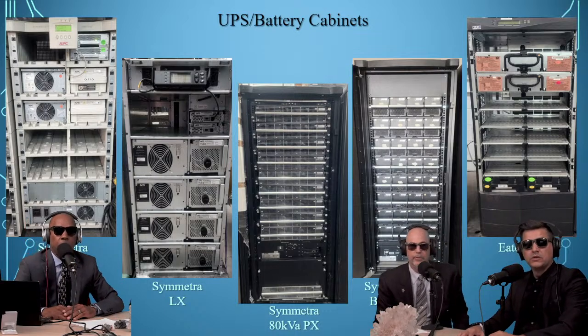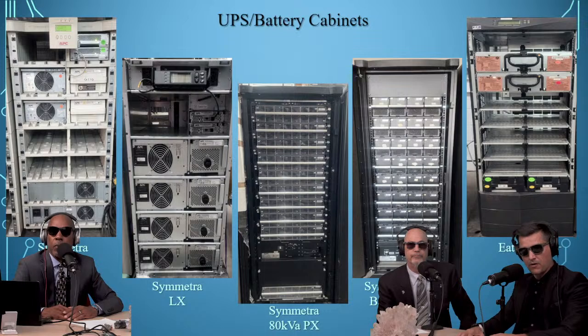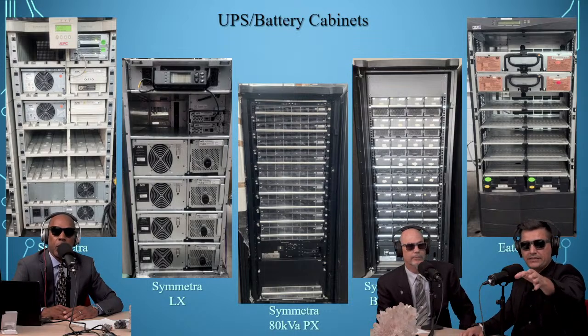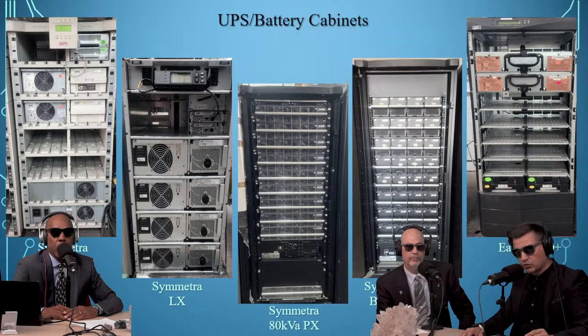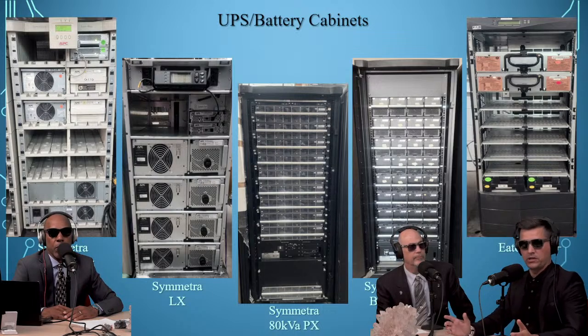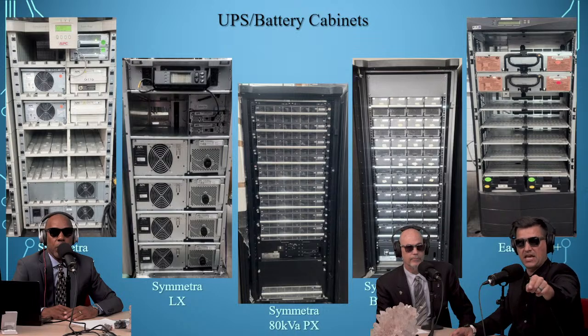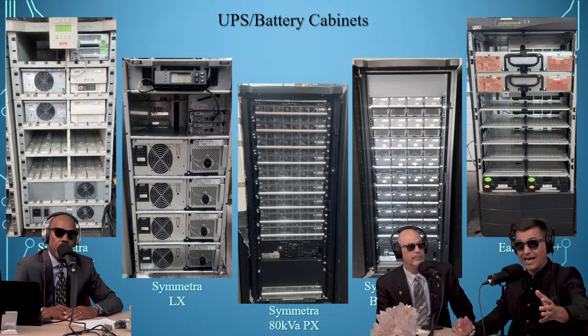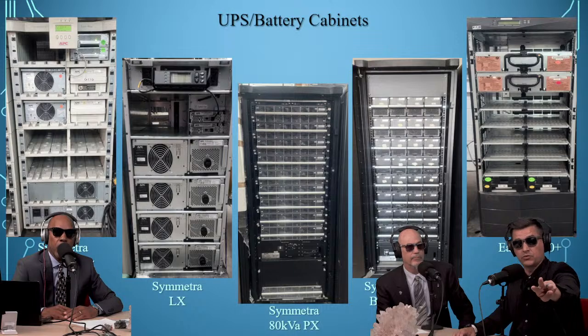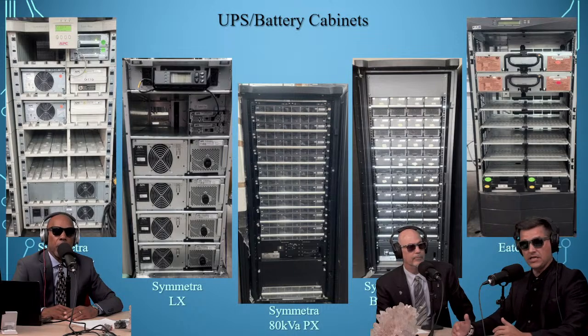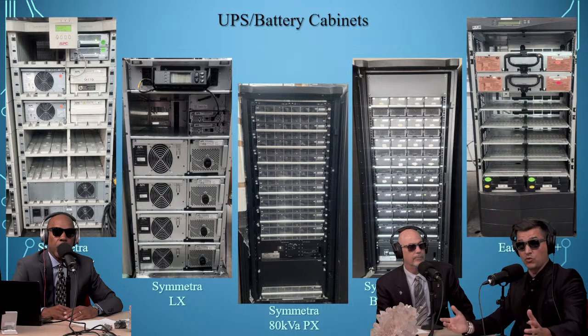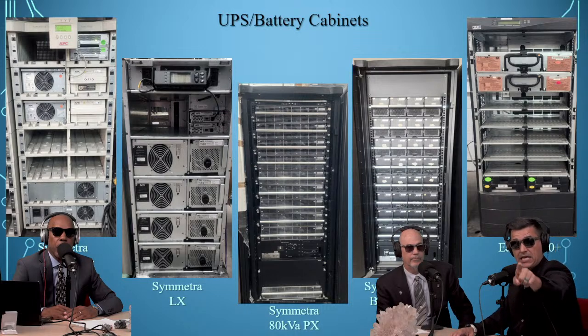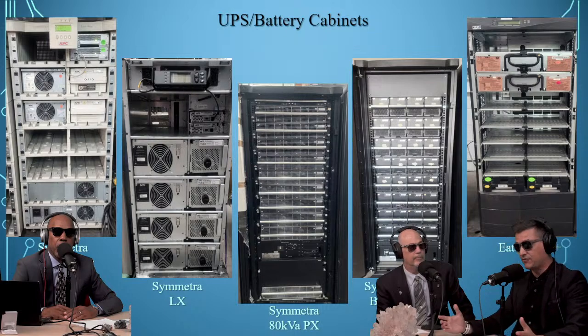Absolutely. So how many power modules do you need in a UPS to be powered on? That depends, and here's why. Let's say for the LX, where we have 4 power modules, really 5, and then 4 battery modules. The load is the most important thing. For that LX, that's 16 kVA. If you're only running at 2 kVA, you only need 1. But if you're running at 6 kVA, you'll need 2 power modules. So it depends what load is needed to determine how many power modules you need. If it's only 5 kVA, then for the big 80 kVA unit, you only need 1 power module because that gives you 10 kVA of power.